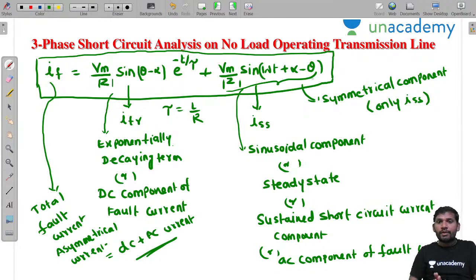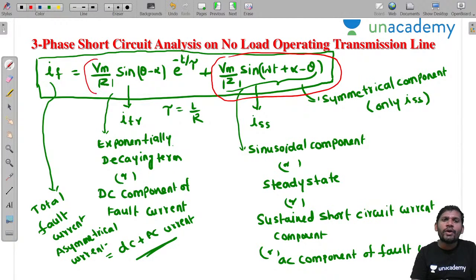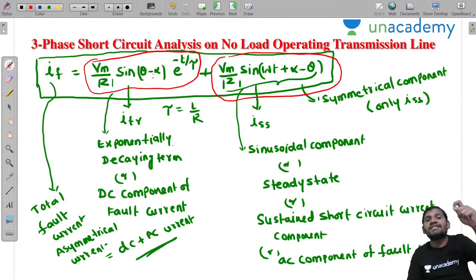Now, if you consider only this component, it is a symmetrical component. But if you consider only this other component, it is a DC component. By adding this DC component and symmetrical component, it becomes an asymmetrical current. So the main reason for asymmetrical current in the case of a three-phase short circuit fault of a transmission line is the DC component of current.